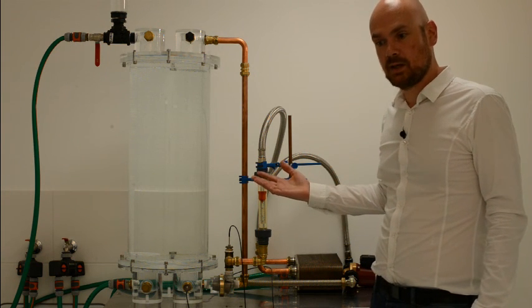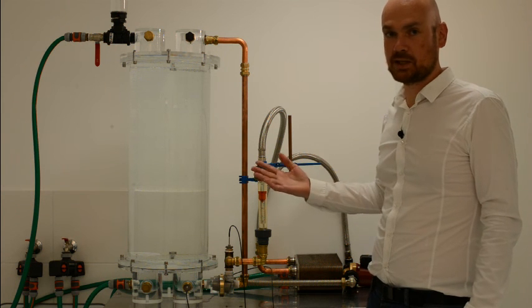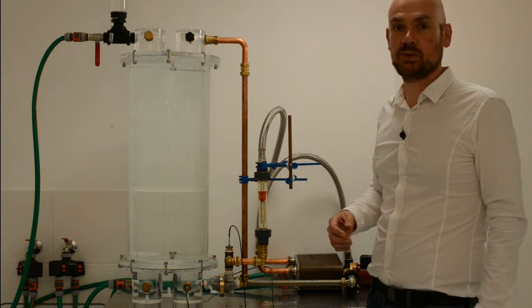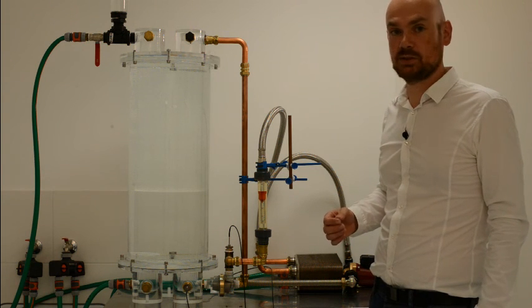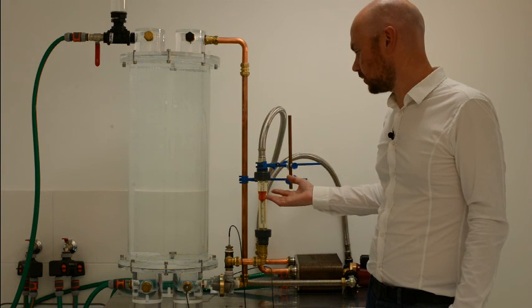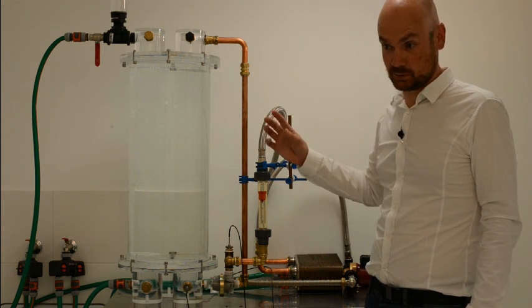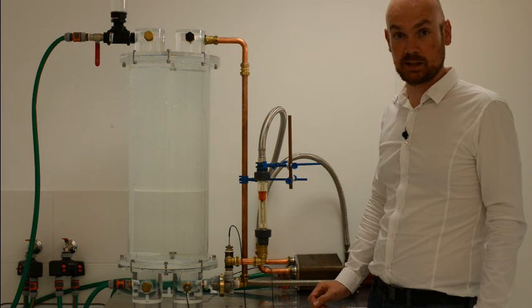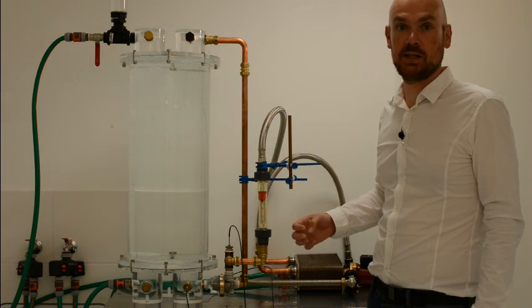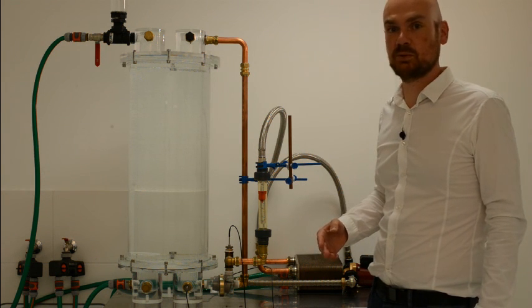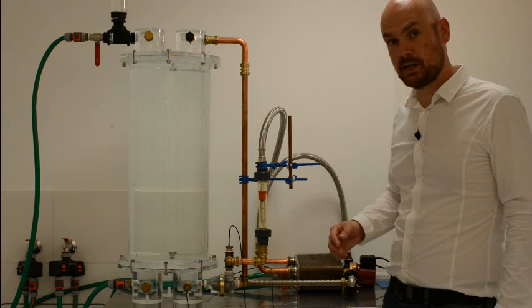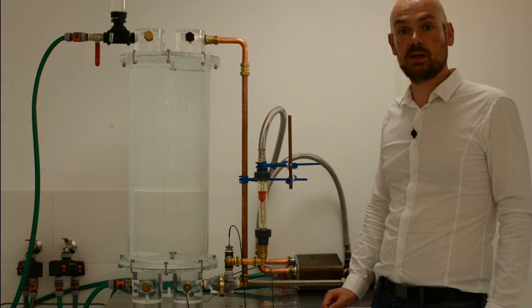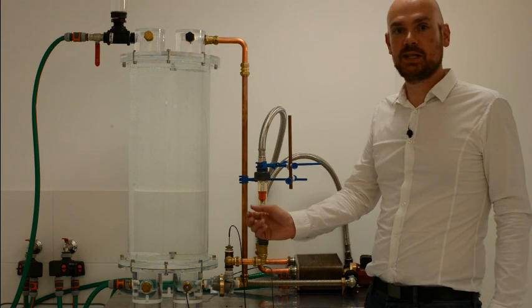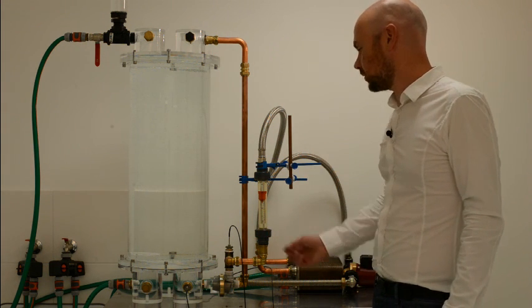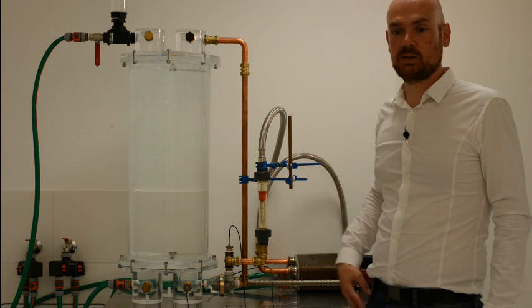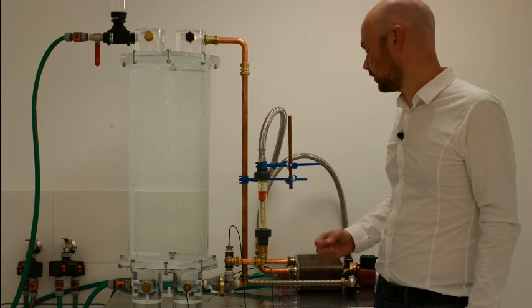And as you have seen, the valve is very accurate in switching and will thereby also increase the efficiency compared to when using a system with a differential controller, because the system will be able to operate at a lower temperature, as it requires only less than 1 degree temperature difference before it can collect heat, instead of the typical 6 degrees that a differential controller takes before it switches on. And more importantly, any cold water that is in the pipes at the startup of a solar system will not go into the tank as with a conventional system, but will be bypassed, so that you avoid a lot of heat losses in the piping by using this valve as well.